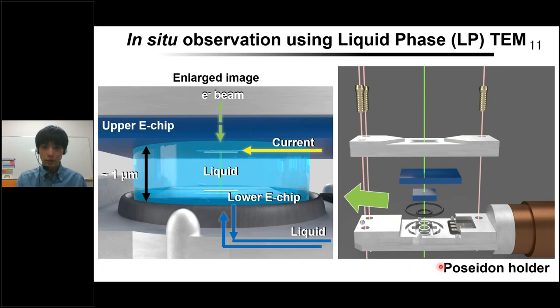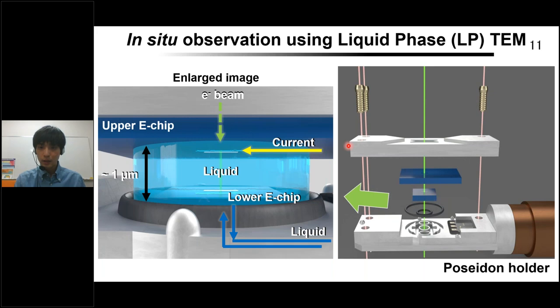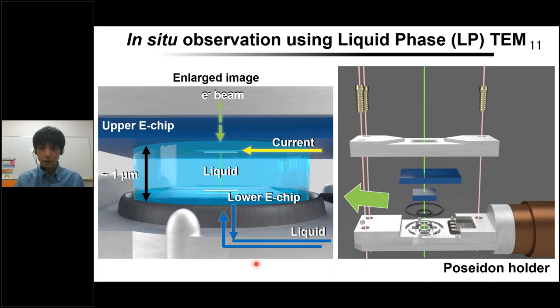Normally, we evacuate the TEM to avoid the scattering of electron beams, so TEM observation requires the sample to be dried. Even if we bring water into the TEM, it will evaporate immediately. Therefore, we use a liquid cell type specimen holder called Poseidon. We use the Poseidon holder as a liquid cell holder produced by Protochips. This Poseidon holder seals and traps the liquid with an O-ring and two silicon substrates. The silicon nitride membrane on the substrate allows electron beams to pass through but does not allow water to evaporate. So we can observe the liquid inside the holder through this membrane.